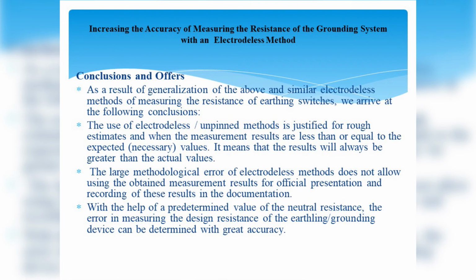The large methodological error of electrodeless methods does not allow using the obtained measurement results for official presentation and recording of these results in the documentation. With the help of a predetermined value of the neutral resistance, the error in measuring the design resistance of the earthing or grounding device can be determined with great accuracy.